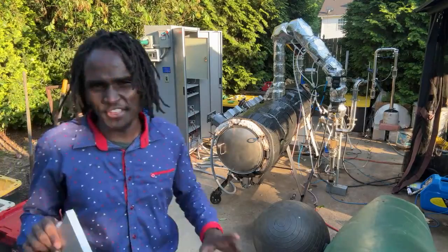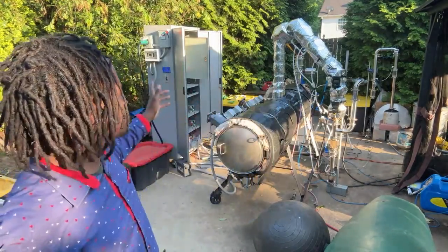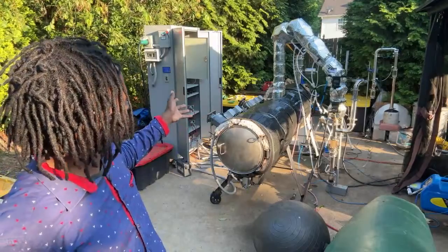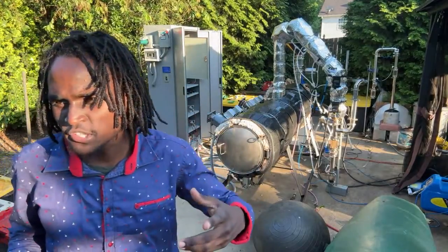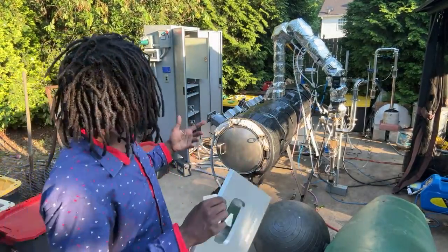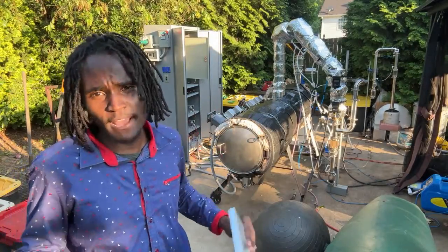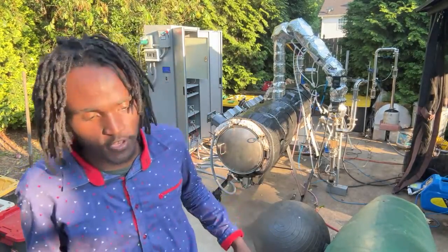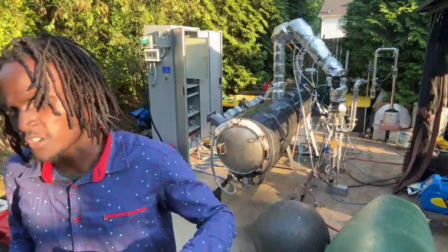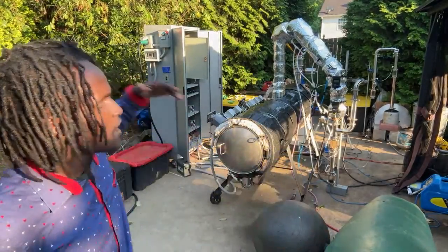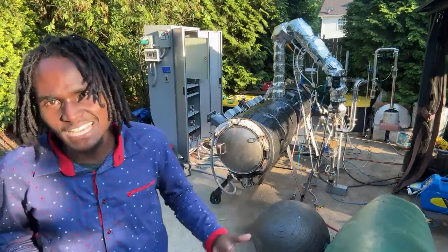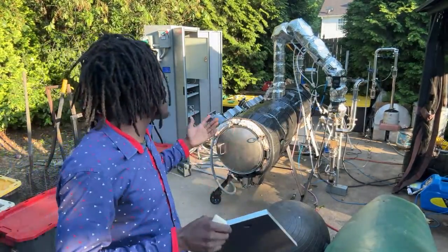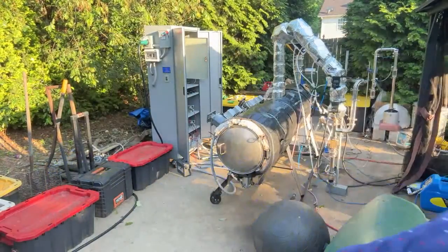I'm going to check something out because I see some vapors, it looks like smoke coming off the back of the machine. I think it's just the fiberglass getting really hot, but you've got to make sure this doesn't just blow up all of a sudden. My vacuum meter is not budging, we're still pulling a consistent vacuum - it's not breaking, so I don't think it's a leak. In fact, if it was a leak, there wouldn't be smoke coming out, it'd be sucked in. So I think it's just something else heating up, but I'm going to check.